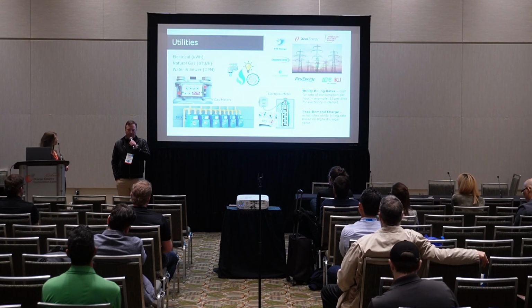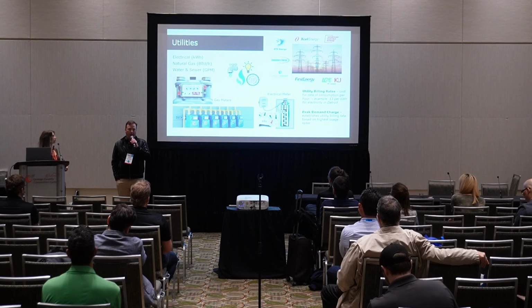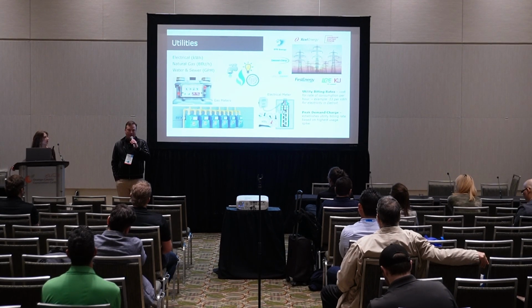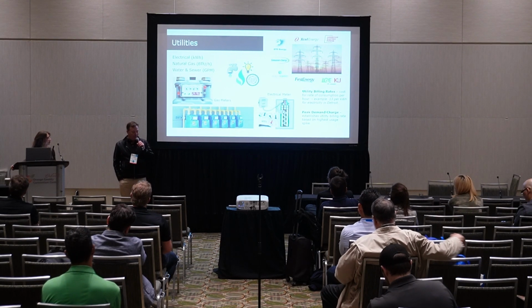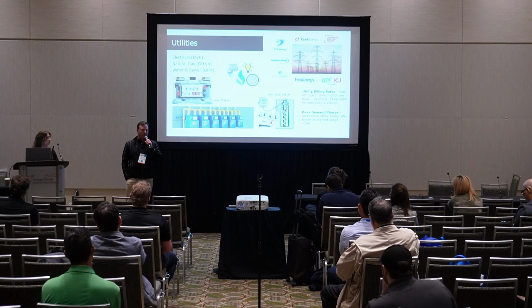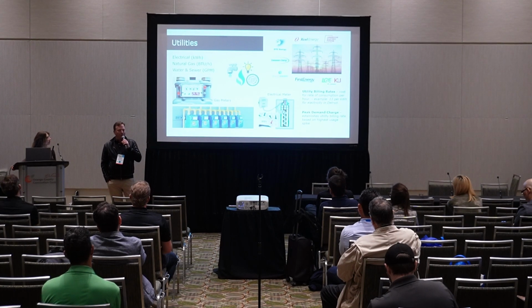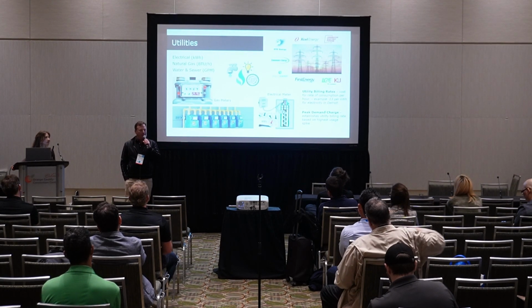As a controls guy, what we don't recommend is automatic load shedding - you put a real-time meter on a building, look at the amp draw, and based on that have your system automatically shut off equipment to alleviate the demand charge. I've seen that done, and of course, whose unit do they turn off first? The president of the company.